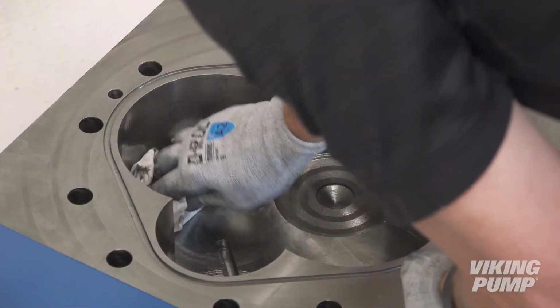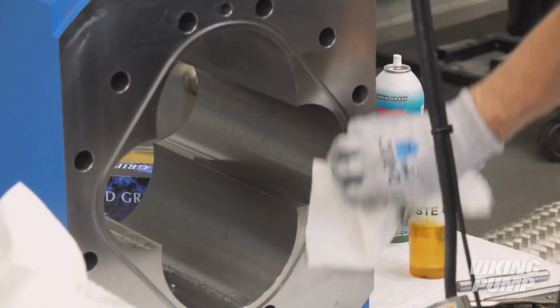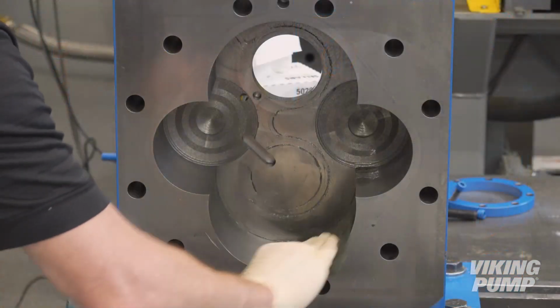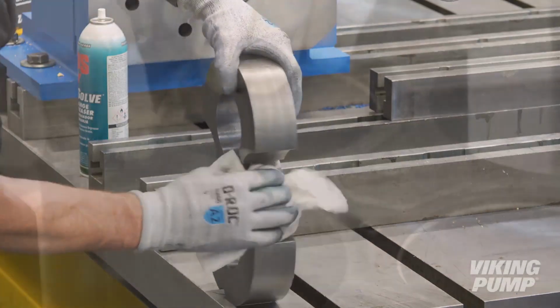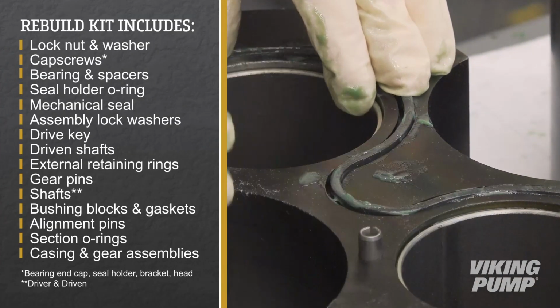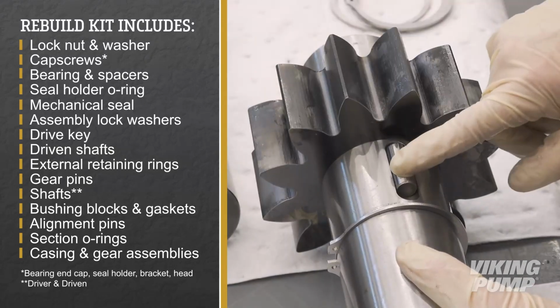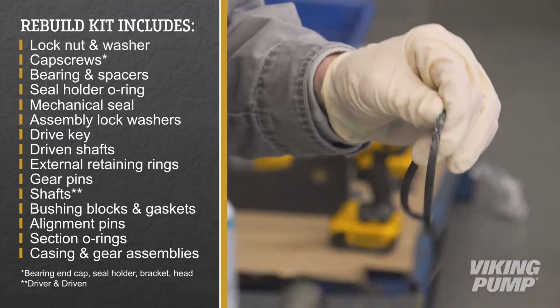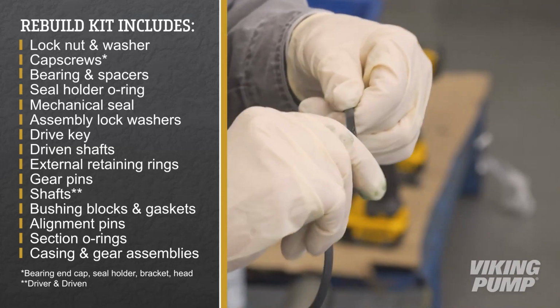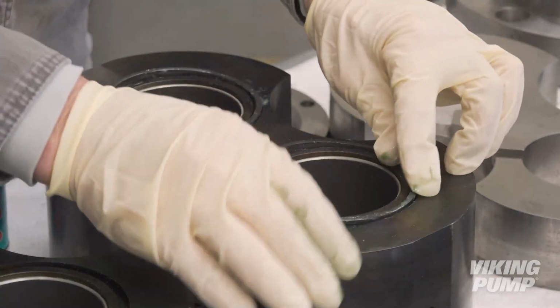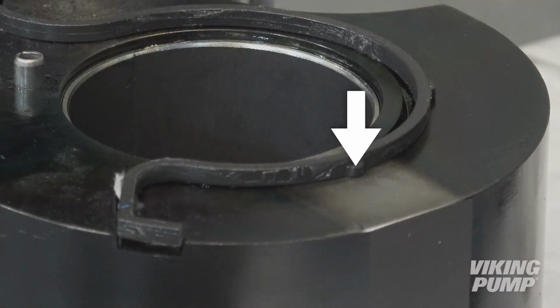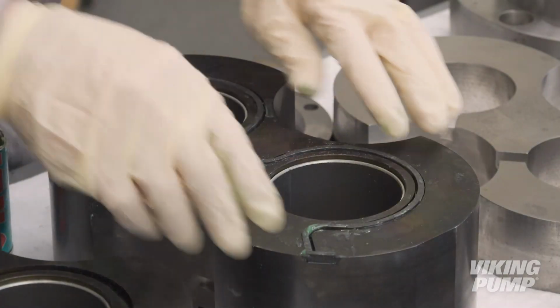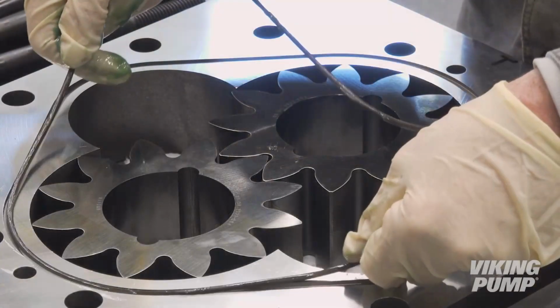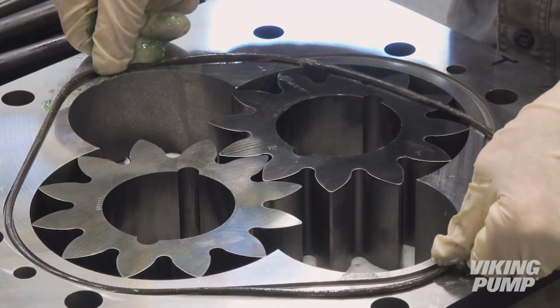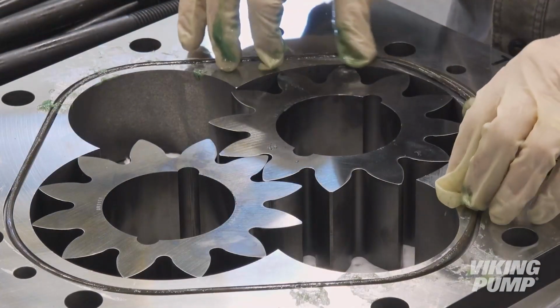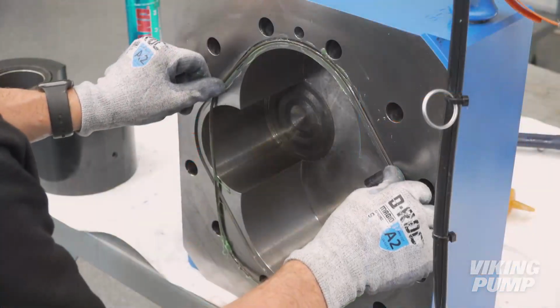Prior to reassembly, ensure the pump head, separation plate, ported separation plate, bracket, and spacers are clean and free of debris. It is recommended to complete all sub-assemblies before starting to rebuild the pump to ensure all components are in place. Begin by applying O-ring grease to the bushing block gaskets and inserting them into the grooves of the bushing blocks with the protrusions down to aid with adhesion. Do this for all bushing blocks and gaskets. Next, apply O-ring grease to the O-rings and insert into the grooves on each pump casing section, on each separation plate, and the pump head.